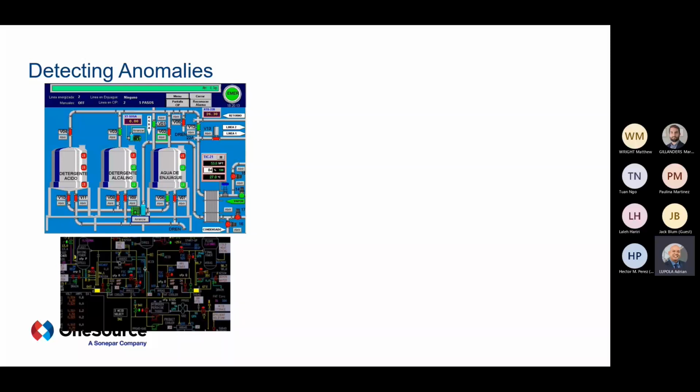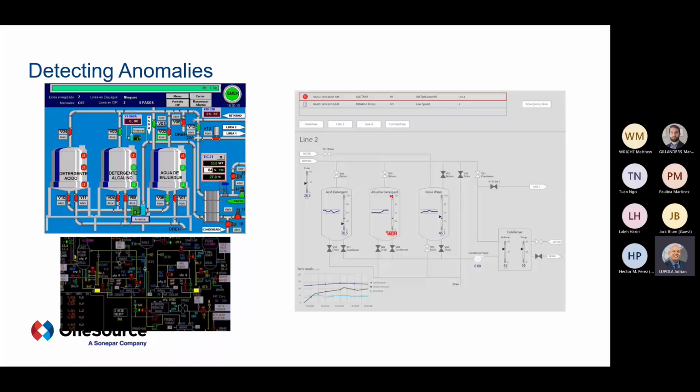They look good, but if you're trying to figure out if there is an issue in your plant or in your system, it's a little harder than if you had a system like this. The system on the right, it's not as fancy with regards to color and whatnot. The only color that pops out is red. However, in this case, boring is good. The reason boring is good, just like the number 5 location in the example we had in the first couple of slides, you can see here that your eyes are drawn to the color red. You're going to look at it, you can see that the tank level is high, and then you have an event up at the top.